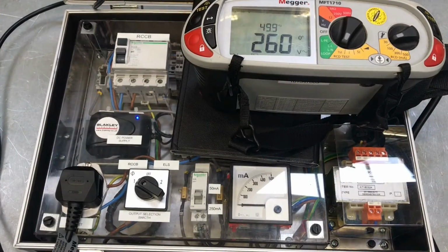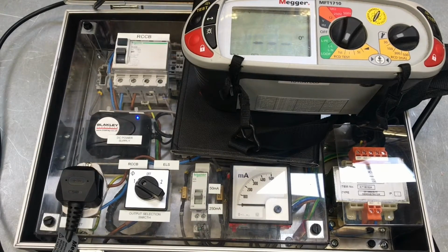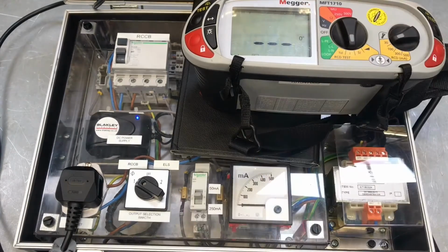Now, any electrician who works on an electrical installation obviously will test the RCD because he's running a supply outside. When he tests the RCD, very simply, he sets it to half times I delta N, pushes his test button, and it shouldn't trip because it's not required to, which is great. It does that on both sides of the sine wave. For speed, I'm not going to.